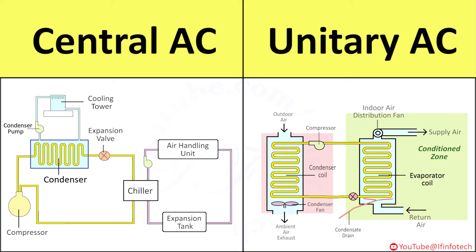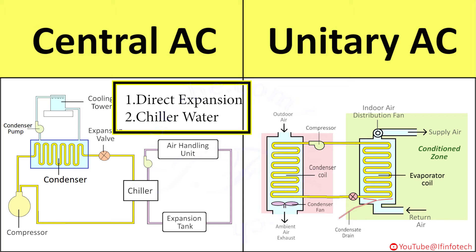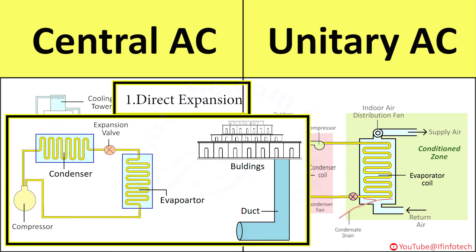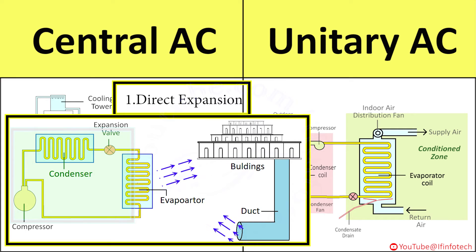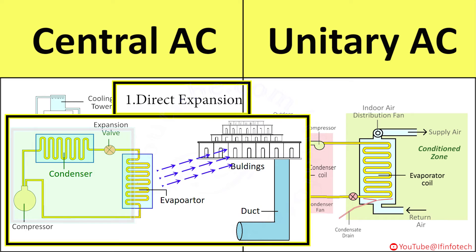Central AC systems are divided into two groups: the direct expansion system and the chilled water system, which is an indirect type. In the direct expansion system, air from the space to be air conditioned is circulated through a cooling coil, which is cooled by the refrigeration cycle. Liquid refrigerant at low pressure absorbs heat from the air and gets converted into vapor. Therefore, it is called a direct expansion system.